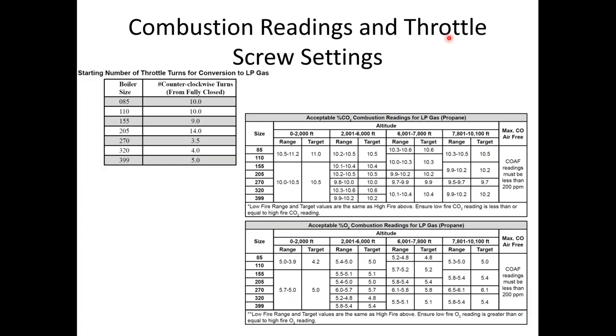These will be your throttle screw settings, and these are just approximate light off points. More times than not, we're usually going to be about 1.5 to 2 turns past where this is when we do our final combustion setup. Often when we do the set, it's out fairly far, but they should light off there. If they don't light off at that point, go a full turn, get kind of heavy-handed, until it lights off. Then we dial it back in with the combustion analyzer.